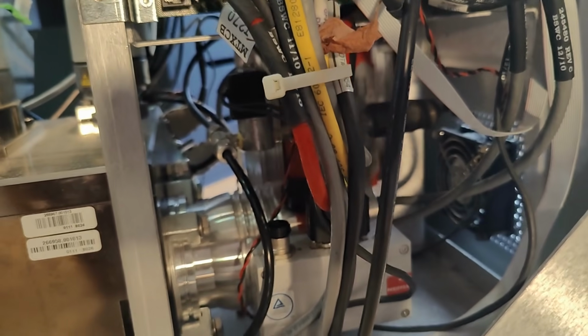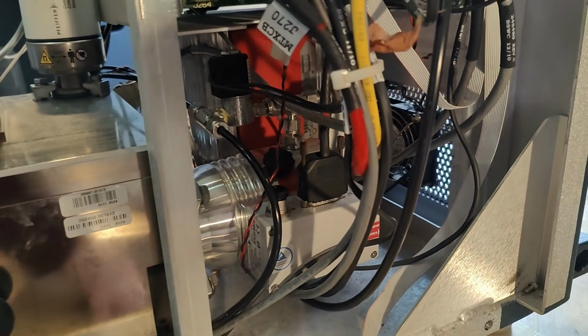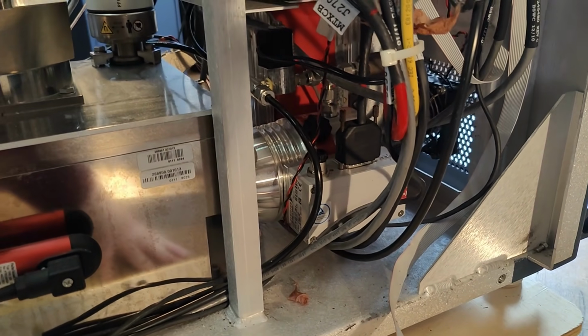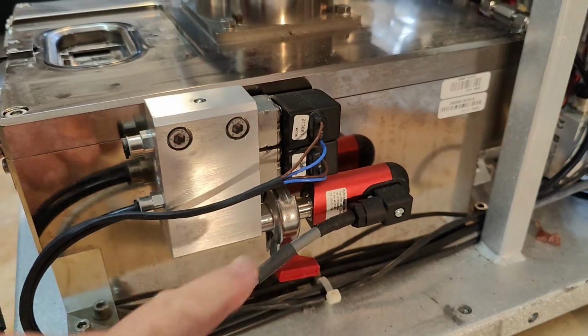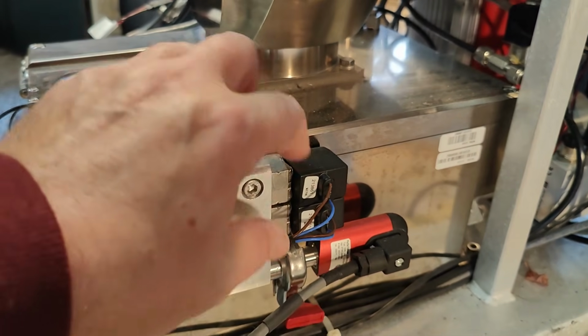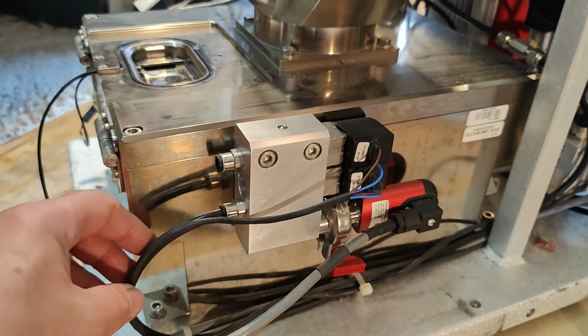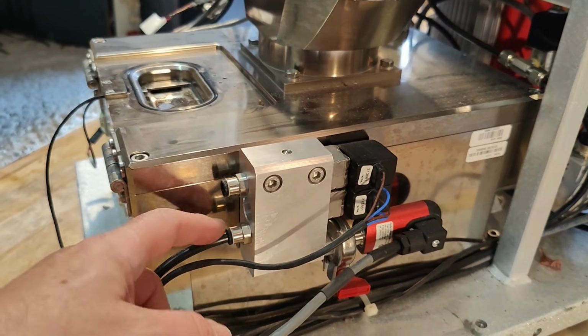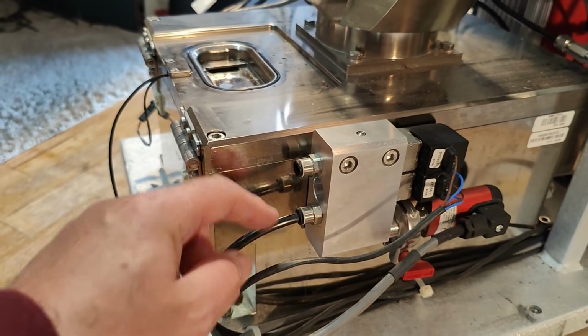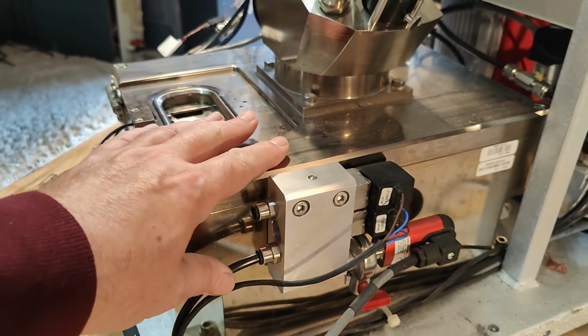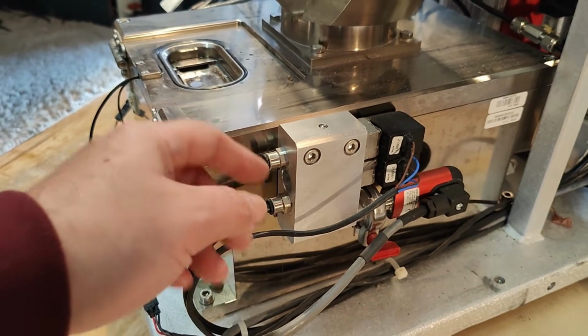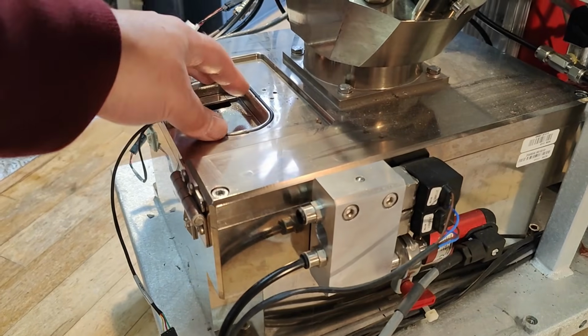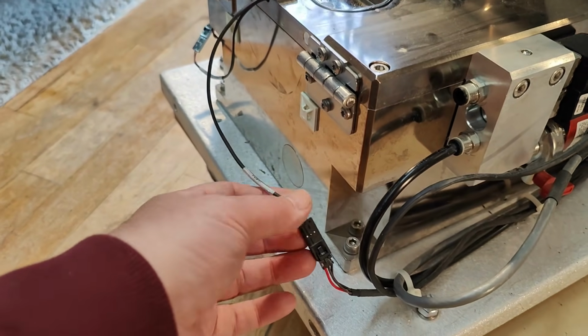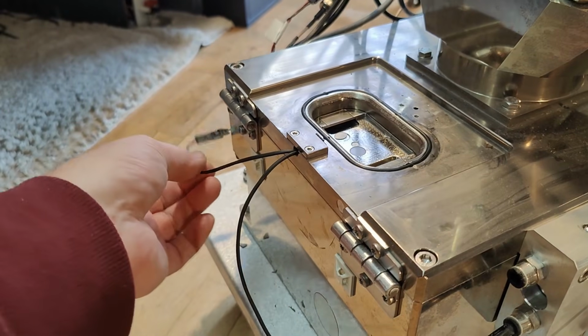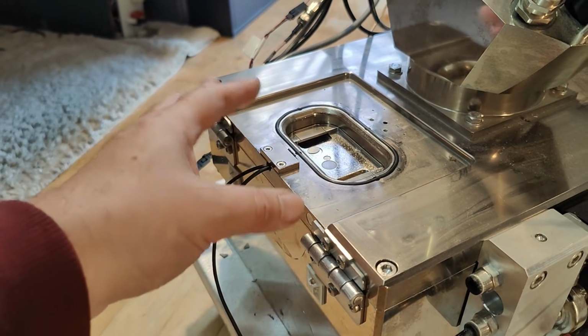We also got quite a lot of vacuum gauges, and that is because there is a lot of automation involved in all this, because you cannot turn on the turbo pump unless you have a certain vacuum. And this is done down here with another vacuum gauge and some valves to open and close for vacuum in and out and all that. And this is of course the vacuum, so you can empty everything. Or actually you fill it up again with air, and then it is non-pressurized, and then you can open the lid and continue. And there's of course some sensors here for the lid that will tell you if you can open or close it, or if it is closed and all that kind of stuff.